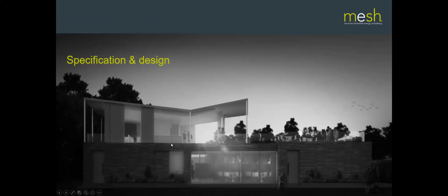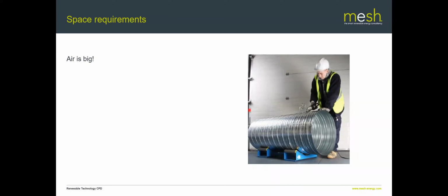So let's talk a little bit more in detail about the specification and design of these MVHR systems. Well, the first thing to bear in mind is that air is big. We're talking about liters per second of air moving around the house, and many tens of liters a second of air. So, as I said, for a 143 square meter house, we're going to need 43 liters per second of air going through. So that means for a typical maybe 200 square meter family home, that's a fair amount of air you're moving around. And of course that air needs to go through some sort of pipe or duct, and that duct obviously needs to be sized to take that volume of air at some sort of reasonable velocity, because if you start making the velocity too high, then it starts getting noisy.